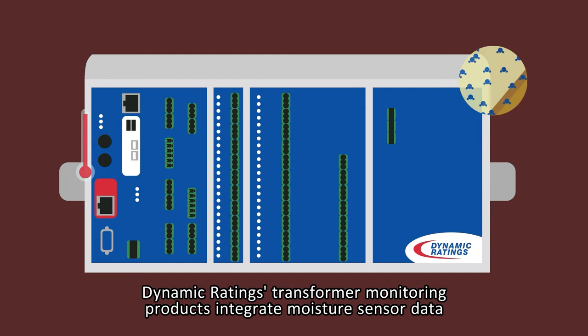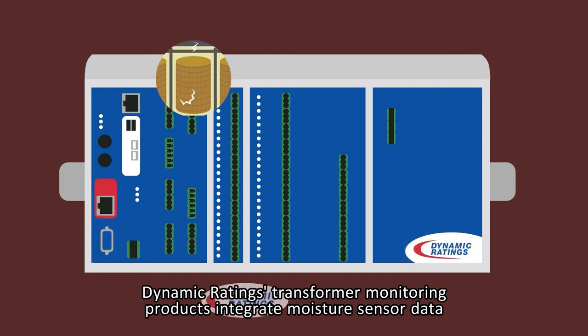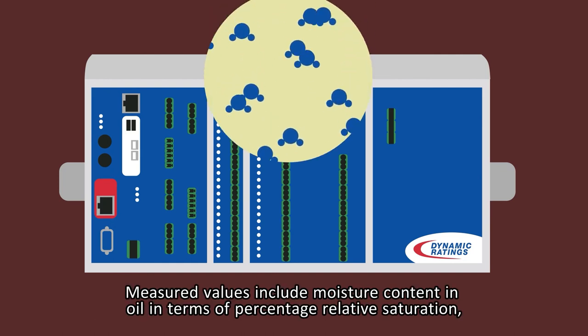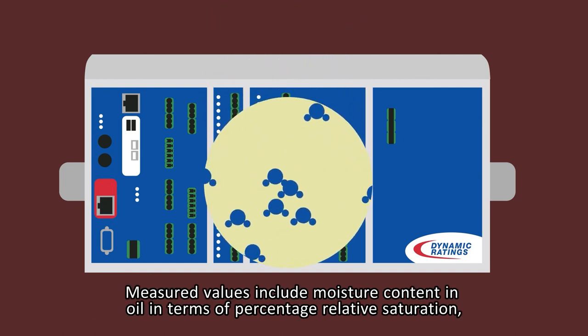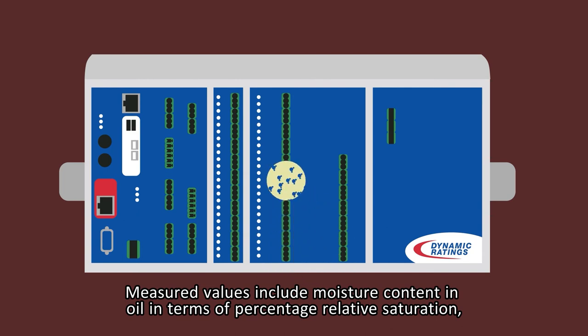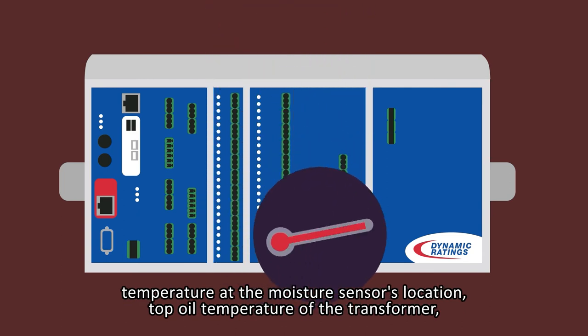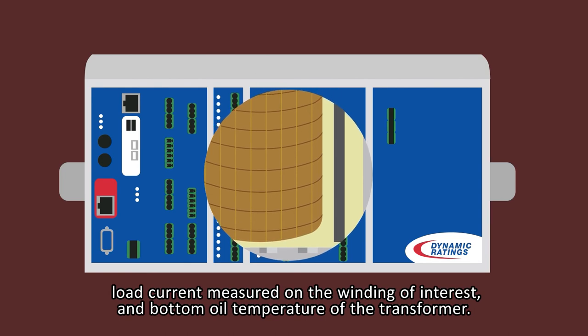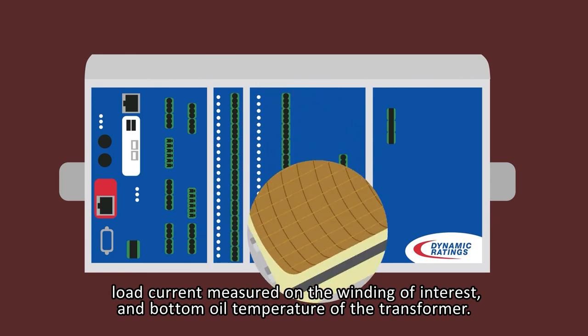Dynamic Ratings transformer monitoring products integrate moisture sensor data and other parameters as part of the moisture management model. Measured values include moisture content in oil in terms of percentage relative saturation, temperature at the moisture sensor's location, top oil temperature of the transformer, load current measured on the winding of interest, and bottom oil temperature of the transformer.